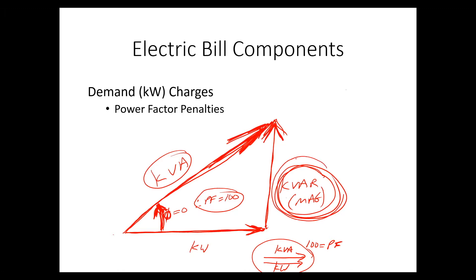Okay, so just to review, we need this KVAR, this magnetic energy, to basically start the motor. But once we get it started, we want to minimize this KVAR because it is basically making the utility do more work in supplying us KVA.